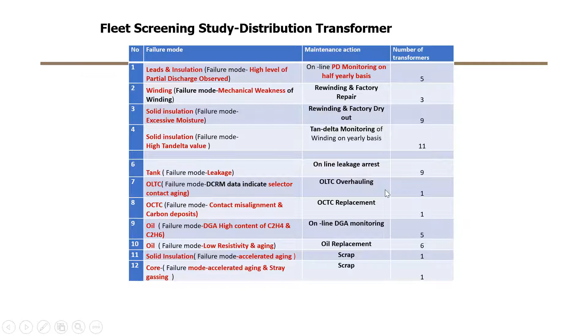Oil: if you have a high DGA, then you need online DGA monitoring. If the oil itself has low resistivity and aging, that means you need oil replacement. If there is aging of the solid insulation, DP is already very low, furan content is high, then scrap it. If you have a lot of stray gases and more aging of the core, then scrap it. So these were the maintenance actions based on the fleet assessment, because based on these maintenance actions, the cost could be optimized, the value could be achieved, and the next hierarchy can be made. And these are a number of transformers which were showing the same kind of symptom. So based on this, you can make a very nice FMEA table in detail, and you can calculate risk from here itself.